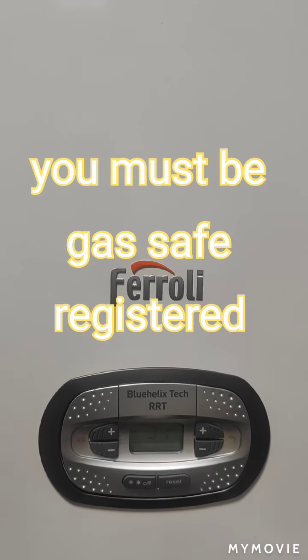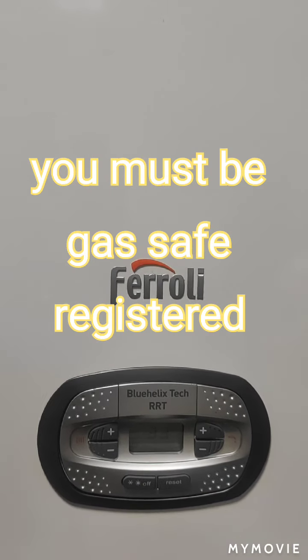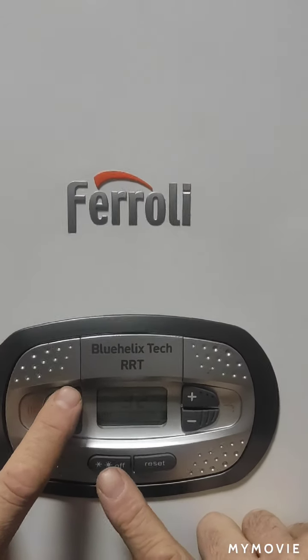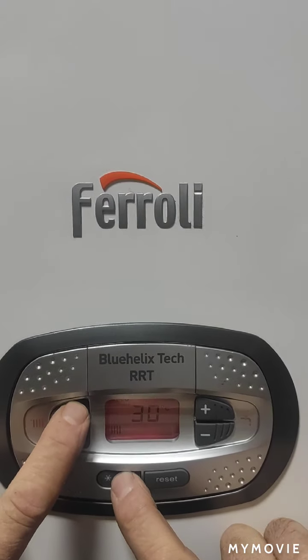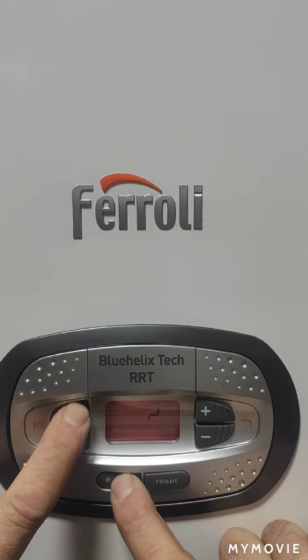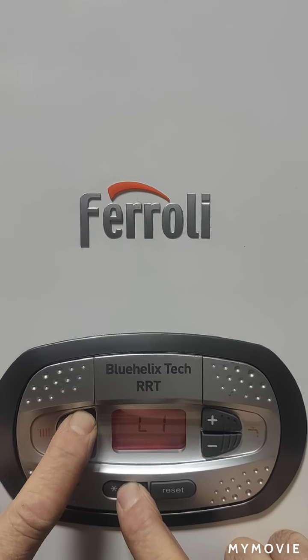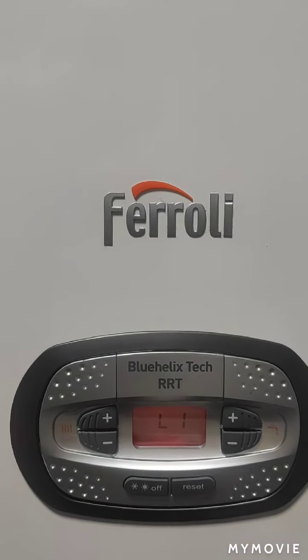So this one, for argument's sake, you've changed a gas valve or you've had to change a circuit board for whatever reason, you have to do a calibration mode, so the circuit board and the gas valve speak to each other and start getting the proper readings. So we've got the plus button and the off button, press them in both together. Here we'll come up calibration.